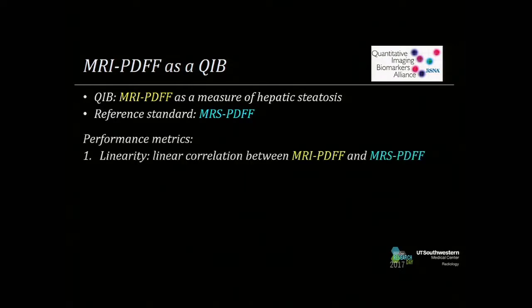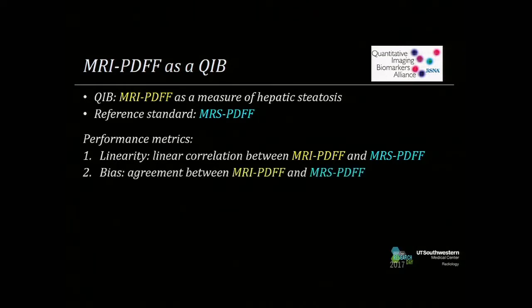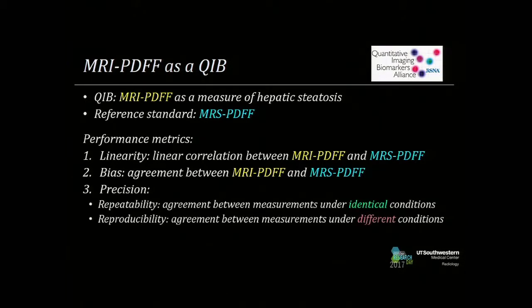The performance metrics are going to be linearity — the linear correlation between MRI-PDFF and MR spectroscopy — and bias, which is the agreement between the two measurements, as well as precision. For MRI-PDFF, that means repeatability: agreement between measurements under identical conditions, scanning and re-scanning a patient. And reproducibility: scanning a patient under different conditions — different magnet, different vendor, et cetera.